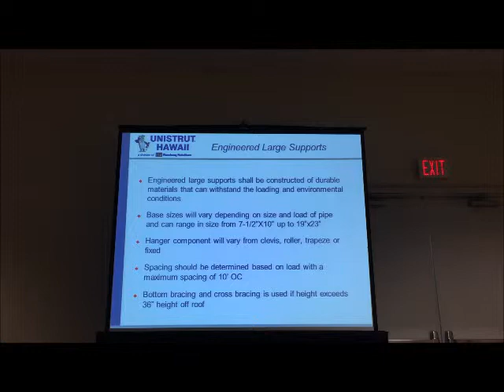Now, large pipe, you're a mechanical contractor. The larger the pipe, naturally, the farther the spacing, because the pipe itself is stronger. A 10-inch pipe, you can support that, and it'll maintain level. It won't deflect too much over a 10-foot span compared to a 2-inch pipe.